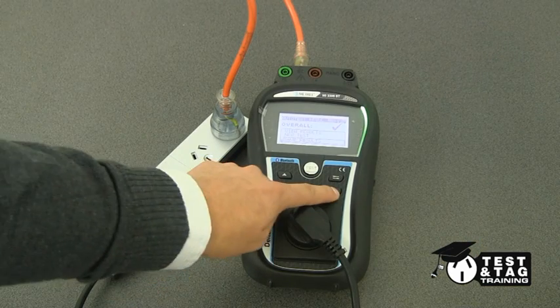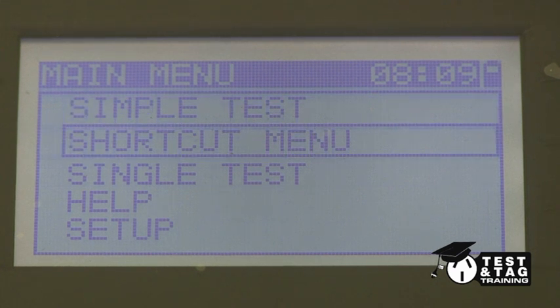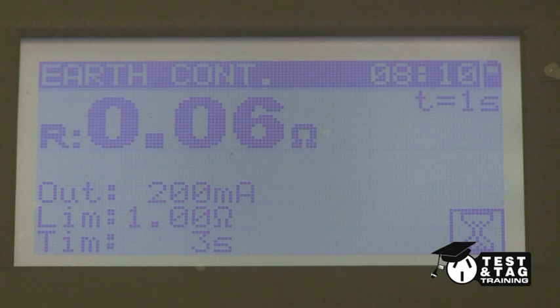The Metrel testers can be programmed in many ways, and if you do not have the surge-protected simple test, you can use the shortcut version instead. In the shortcut menu, select Multibox 166. The sequence of this test will include an earth bond, an insulation resistance, and a polarity.